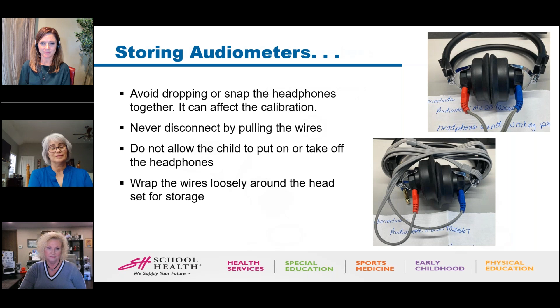Calibration is a very necessary part of hearing screening equipment. And if you're using pure tone audiometers, you never want to interchange the headsets because they are specifically calibrated to that audiometer. So if you've got a malfunction or you think something's wrong with your headphones and you've got multiple units, you can't just take the headphone from one and put it on the other, because you're not going to get the right calibration, and it's not going to potentially work for your hearing screenings. So it's a big thing to keep in mind. Don't interchange those. The other thing with calibration is that it's recommended to do the calibration yearly, every 12 months. You can extend that a little bit, but having your device calibrated is extremely important.